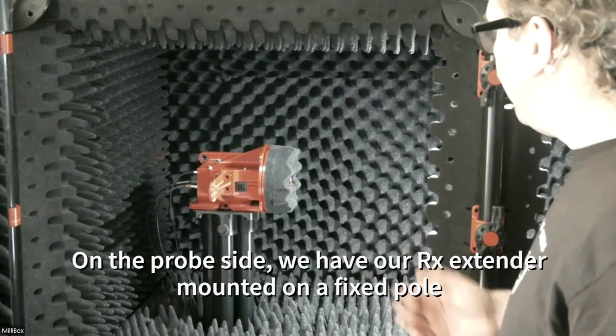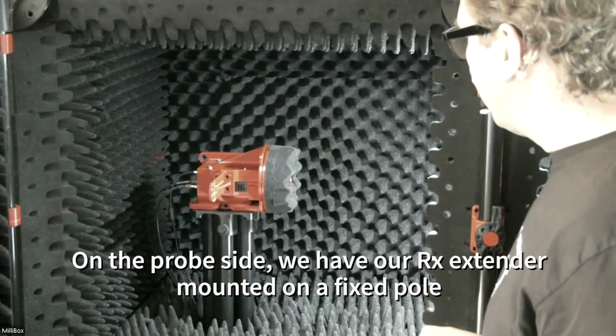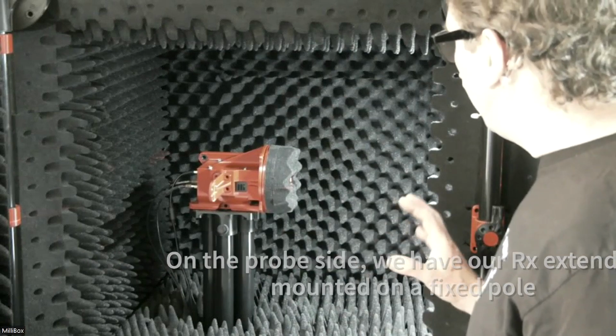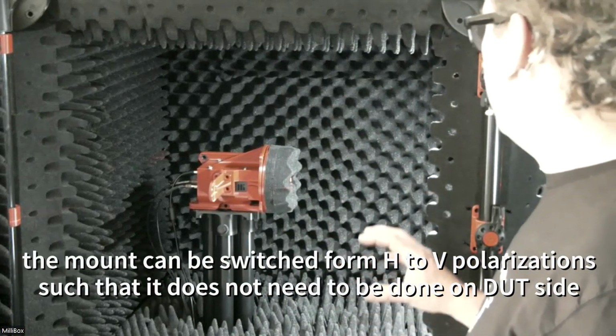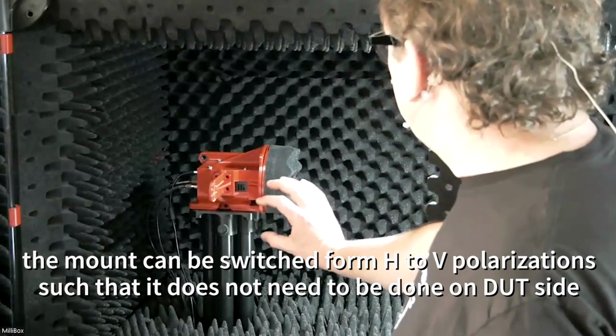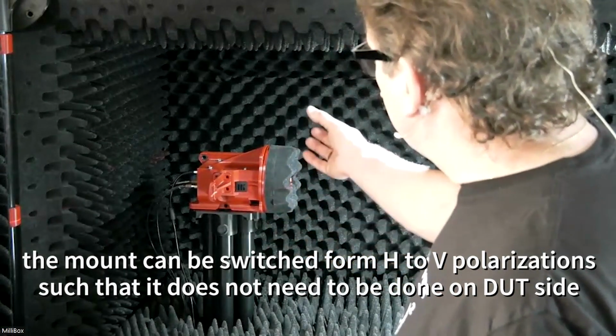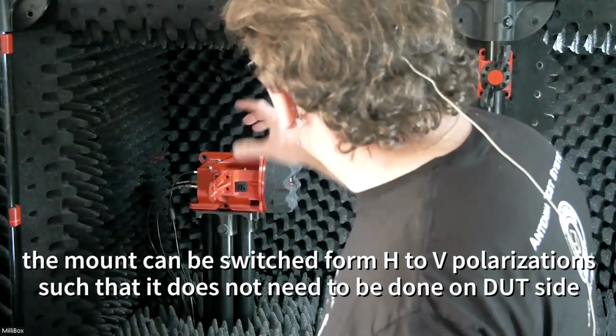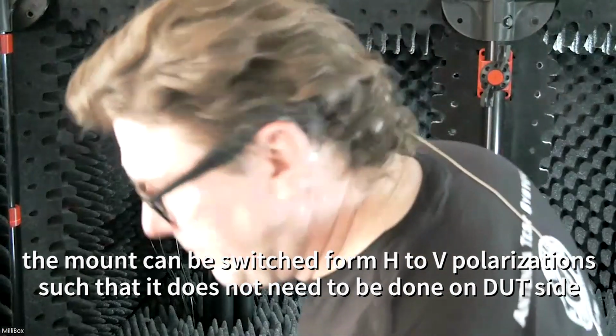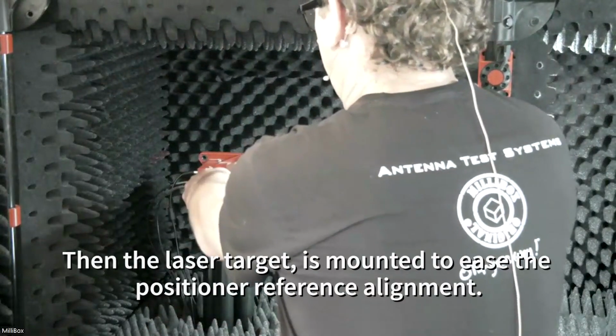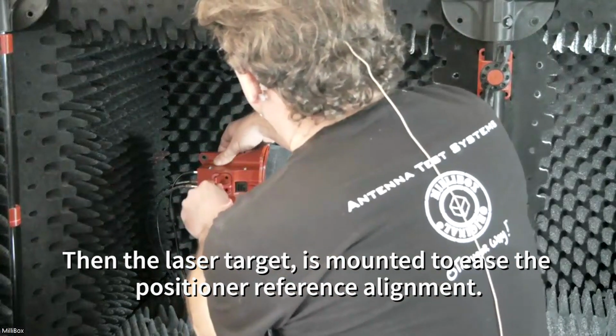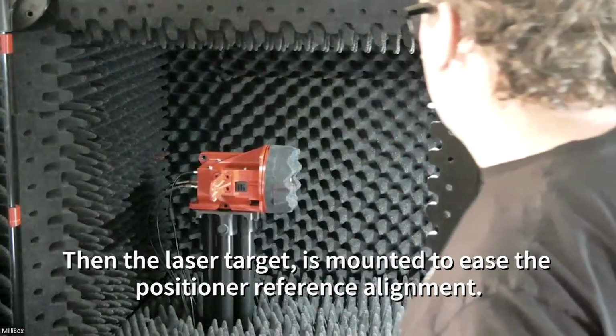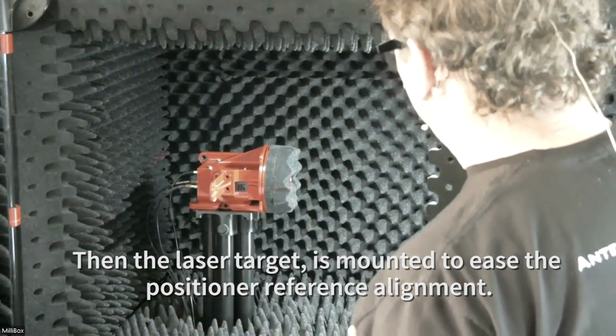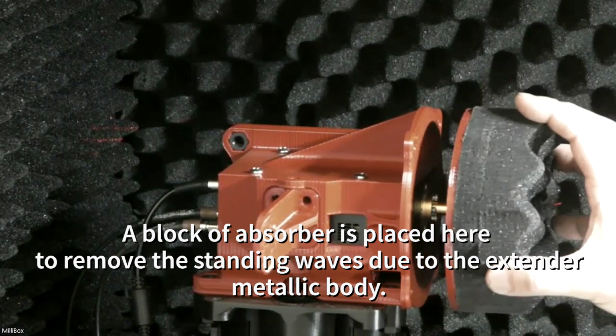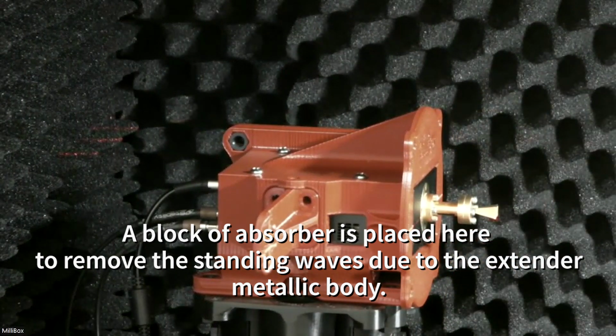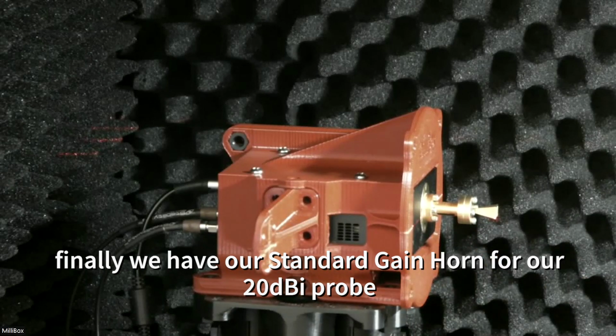On the probe side, we have the other side of the frequency extender. So in our case, that's our RX. We have a fixed mount, which allows us to place the extender in 90-degree polarization. So you can mount it this way, you can mount it vertically, and you have a laser target adjusted to make the alignment with the transmitter. Here we have a block of absorber that's to limit the standing wave surface of the extender. And we have our reference probe. Here we have a 20 dBi WR6.